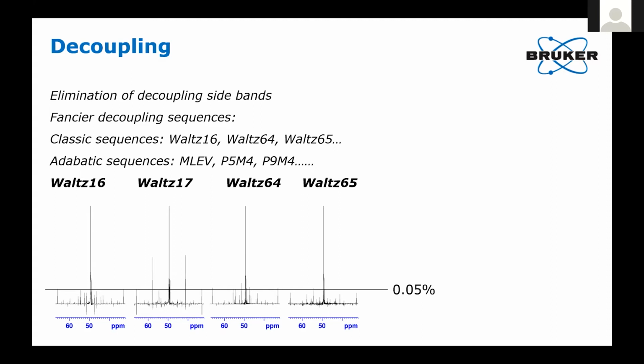If you look here, we start on the left with a simple WALTZ-16. That gives us a sideband pattern. By the way, this is carbon-13 labeled methanol, so I get a huge peak and I see those small peaks. We're at about a factor of 10 below what would be a satellite height if you have more than one carbon in there. You go to WALTZ-17, you can see you change the pattern. You go to WALTZ-64, you again change the pattern, and WALTZ-65 gives you one of the cleanest sequences without going to fancier schemes. Of course, there are adiabatic sequences, or decoupler sequences which use adiabatic pulses. You can put them in an MLEV supercycle or a P5M4, P9M4.